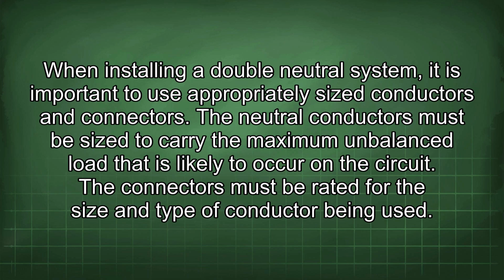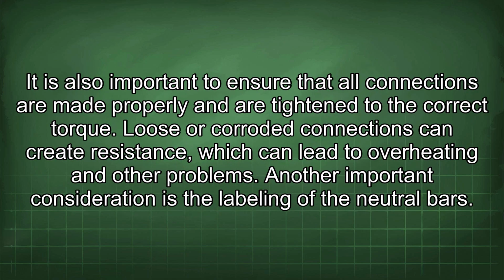The neutral conductors must be sized to carry the maximum unbalanced load that is likely to occur on the circuit. The connectors must be rated for the size and type of conductor being used. It is also important to ensure that all connections are made properly and are tightened to the correct torque. Loose or corroded connections can create resistance, which can lead to overheating and other problems.